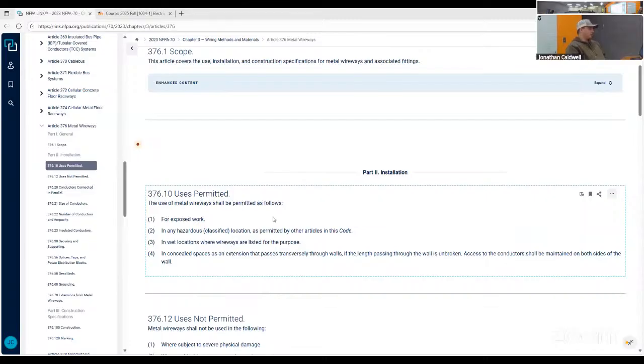Use is permitted for exposed work in any hazardous classified location, as permitted. In wet locations where wireways are listed for the purpose, and concealed spaces as an extension that passes transversely through walls if the length passing through the walls is unbroken. Access to the conductor shall be maintained on both sides of the wall. Can anyone explain to me what that means? It explains it really well, but I just want to make sure everyone understands what that's actually saying.